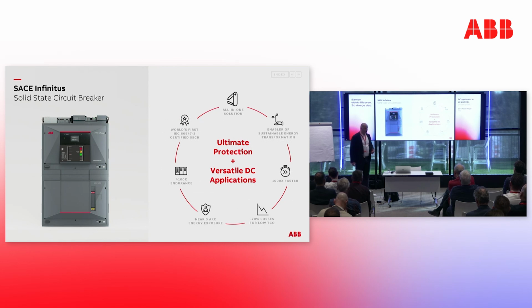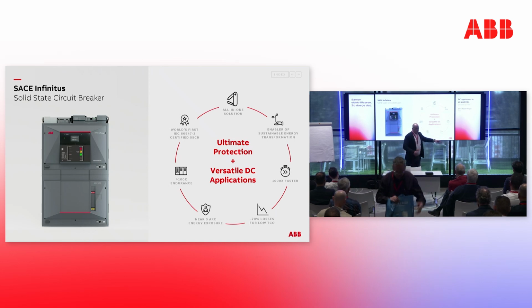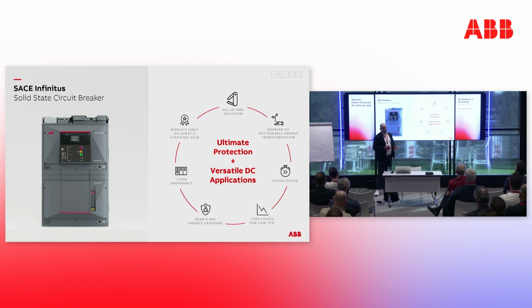ABB has its own first solid-state circuit breaker. As with all solid-state circuit breakers, it is very fast. What is a little bit different is that it uses an optimized semiconductor that reduces losses significantly compared to other solid-state circuit breakers. Just to give you a rough idea, this circuit breaker has approximately 1 volt voltage drop at 1000 ampere. If I use 2 IGBTs connected anti-series, then at the same current I will probably have around 4 volts, if not more, depending on the temperature. Maybe 3, depends on the IGBT, but it's quite a big difference.